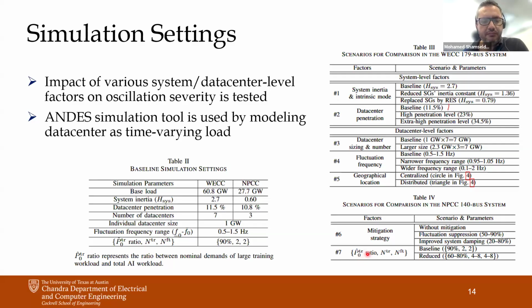We set the penetration level based on the base load, which did not consider the size of the data center, so it could be a little less than 10% once we combine the base load and the data center load. In most regions the penetration level of data centers has not reached 10% and is much lower. But in some specific regions in North America, there are areas with a very high penetration level of data centers, which is why we mostly considered North American grids for our studies.